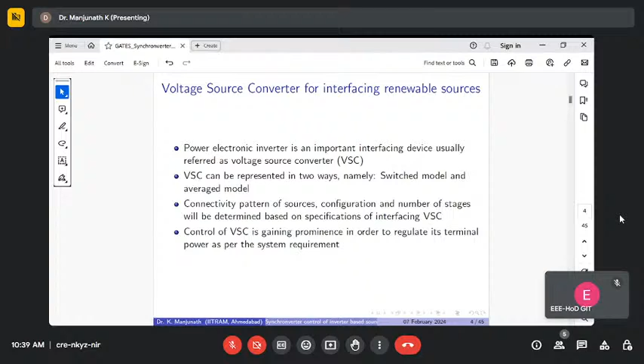Looking at the control aspects of VSC, basically a VSC is driven by a DC source. We give gate pulses to the inverter, obtained by comparing sine and triangle waveforms. This well-known technique is called sinusoidal pulse width modulation. Another technique is space vector pulse width modulation. The terminal voltage magnitude and angle at the AC side of the VSC can be regulated by varying the magnitude and phase shift of the sine wave in the SPWM technique.